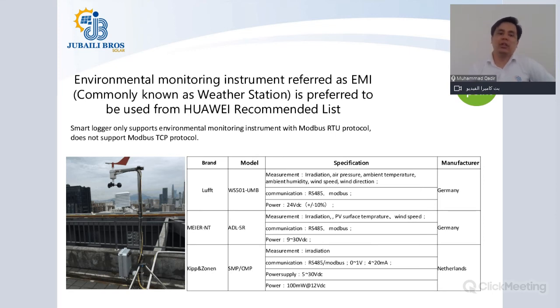And if you are looking at that list and you do not find the weather station which you normally use or prefer to use, you must make sure that the third party, which is not in the HUAWEI library, communicates via Modbus RTU, and then you can configure such a third party weather station in the HUAWEI Smart Logger to read the data. As you all know, these weather stations are normally used for deriving the performance ratio of the PV plant. So make sure you're using one from a renowned brand so that it gives you a very precise value of the weather and you are getting the right performance ratio.